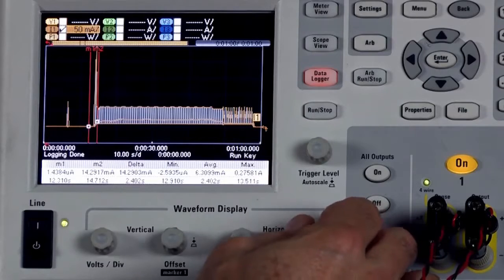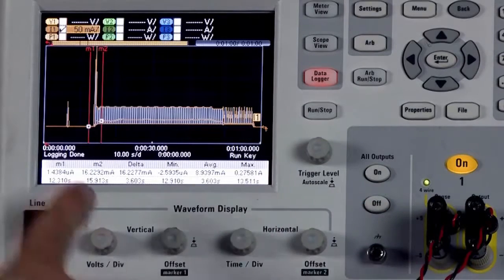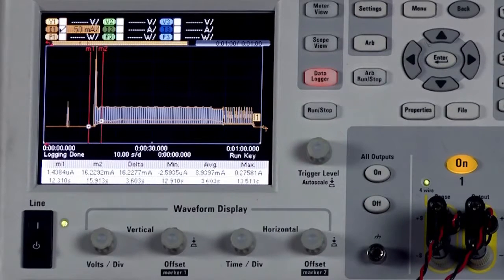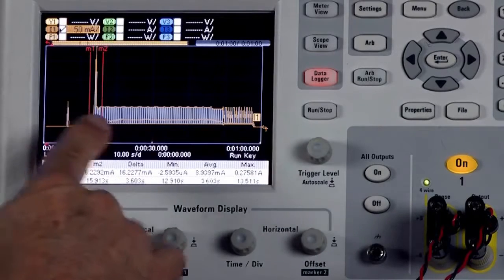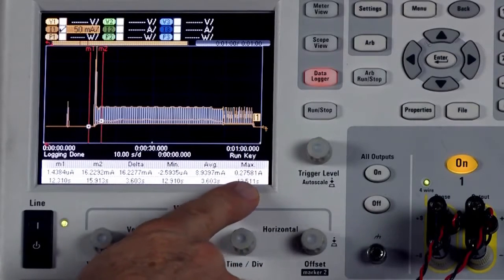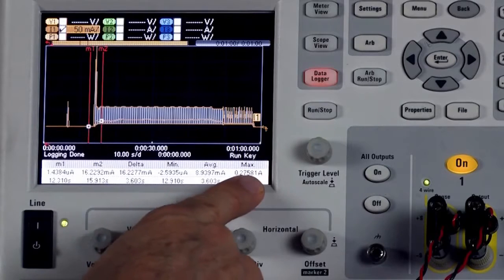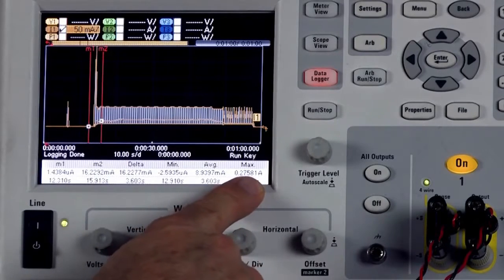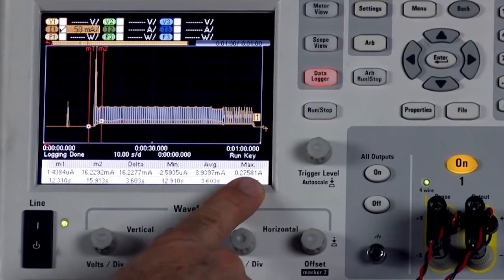What I've set up here first is to look at that spike. That spike is when I turned on the pulse oximeter. And so it was the inrush current that was needed to get it charged up. And if we look at the maximum, or that peak of that spike in between the markers, we can see that it's 275 milliamps. So fairly high level. This would require us to be in the 3 amp range. Again, this is the value of this SMU is these 3 dynamic ranges and being able to change.